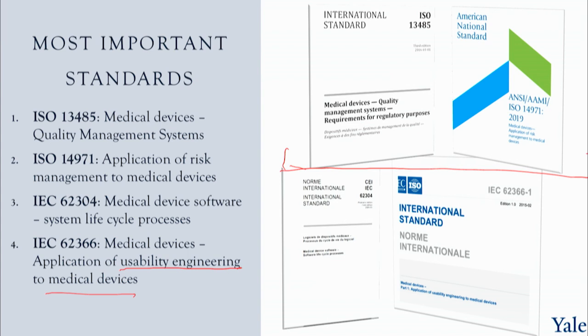And again, these are what Professor Menon said are called soft law. They do not have the force of law, but the regulatory agencies look at compliance with the standards, if you follow the procedures laid out in the standards, as evidence of good work. And these standards are recognized. And so you have a much easier time at many regulatory review processes. You say, well, our software process follows IEC 62304. The agency knows exactly what you're doing, and they're very happy when you say something like that.